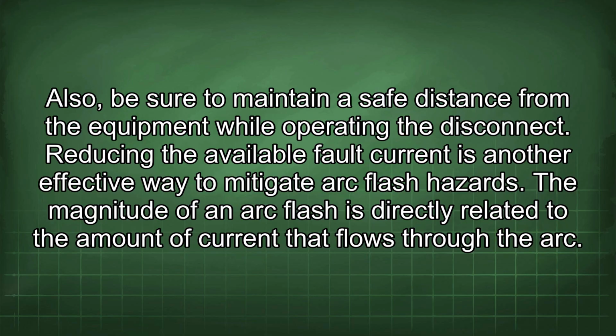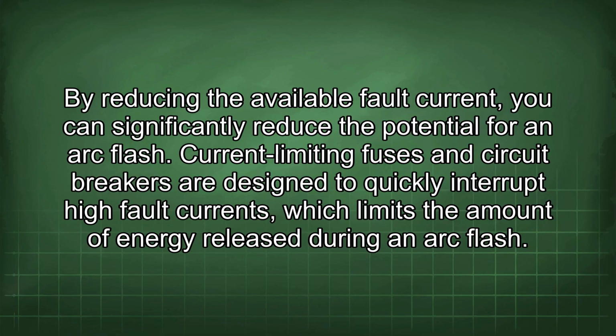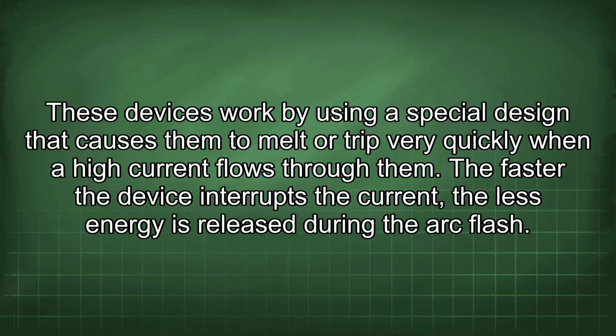Reducing the available fault current is another effective way to mitigate arc flash hazards. The magnitude of an arc flash is directly related to the amount of current that flows through the arc. By reducing the available fault current, you can significantly reduce the potential for an arc flash. Current-limiting fuses and circuit breakers are designed to quickly interrupt high fault currents, which limits the amount of energy released during an arc flash. These devices work by using a special design that causes them to melt or trip very quickly when a high current flows through them. The faster the device interrupts the current, the less energy is released during the arc flash.